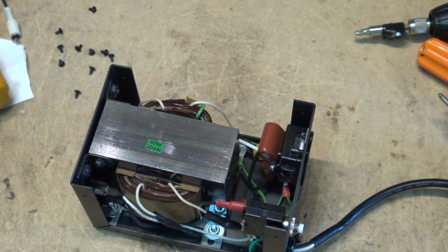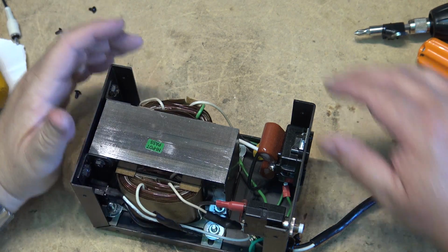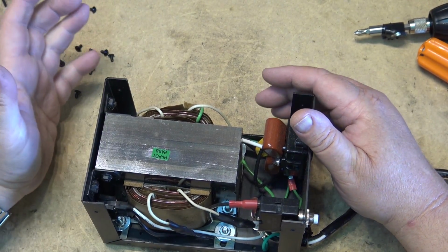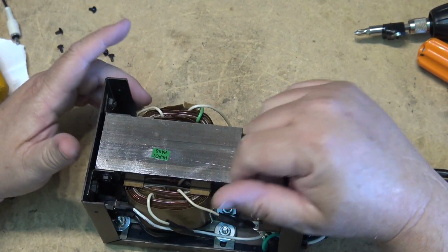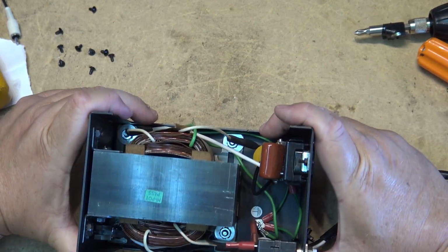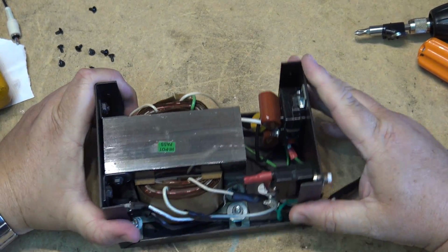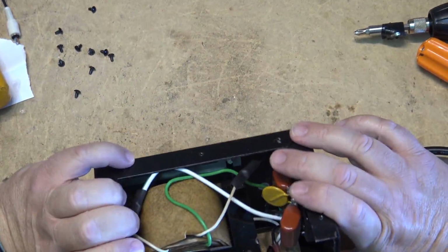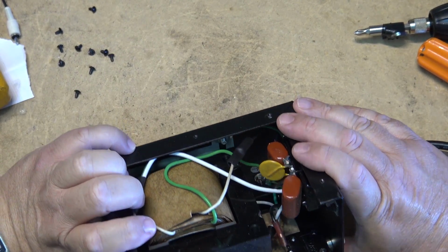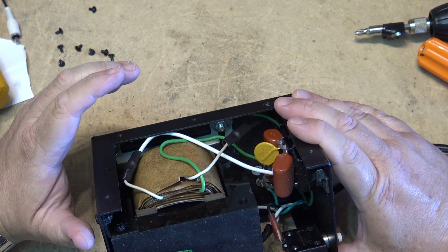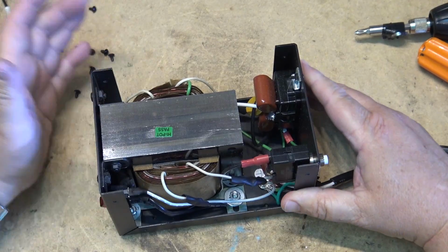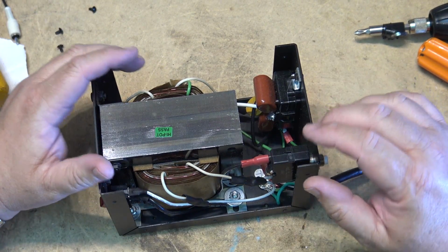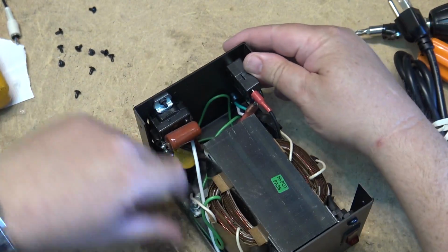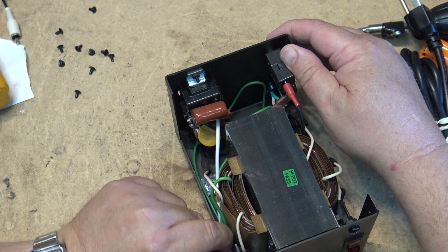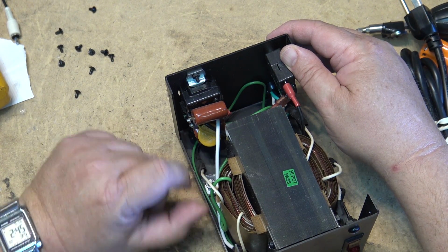So all this is basically a one-to-one ratio transformer. My isolation transformer looks just like that, but it has a cover over it—it's just not in a box like this. What we need to do is isolate the grounds from everything on this that could cause you to get a shock. So we need to isolate the secondary, which is these windings over here—there's your secondary, there's the two windings for the secondary.